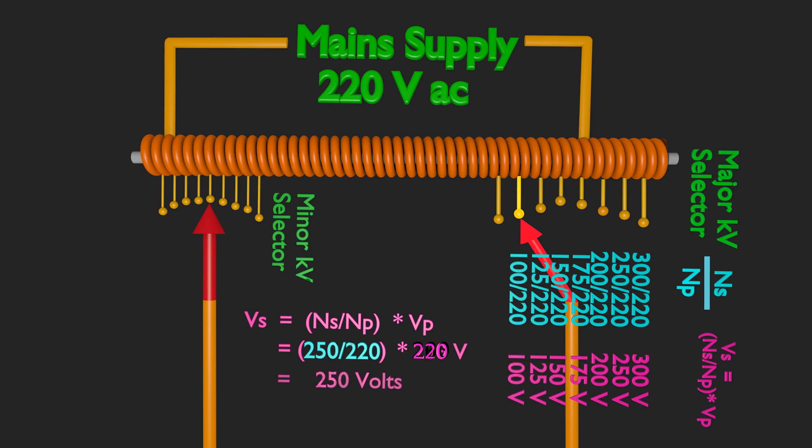While changing one taping to other, voltage variation across secondary is in steps of 25 volts, that is 75 volts then 100 volts, then 125 volt. For voltage variation of 1 volt or less, tapings of minor selector be used.